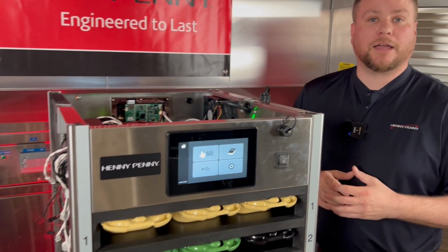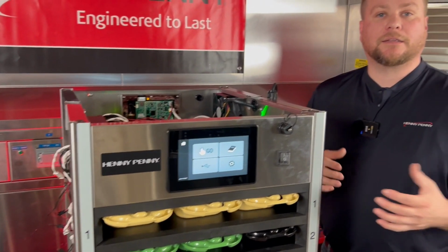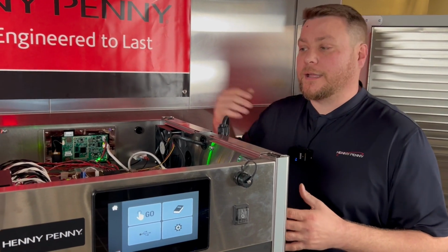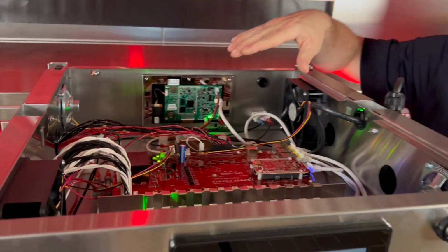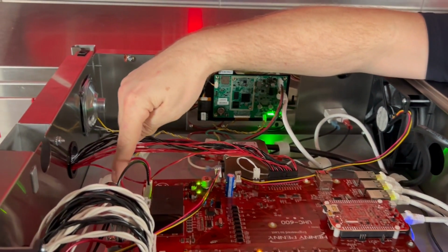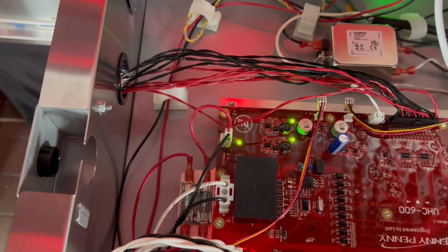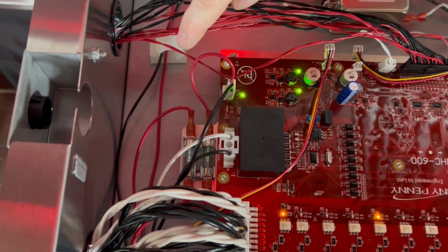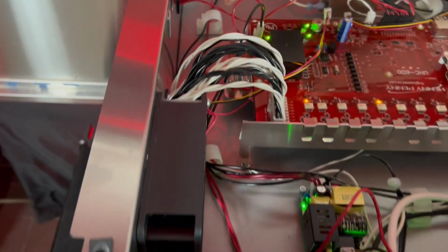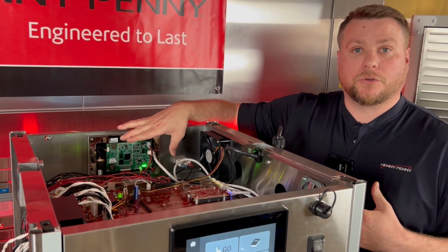However, they will still have access to the control panel so that they can continue to use their timers and navigate throughout the control. Now, when it comes to troubleshooting that, likely we're going to have a situation on the E-220 error code where potentially maybe one of our fuses over here, which is the power supply for our 12 volts DC going to the controls, if one of these fuses is blown, then it will not deliver the 12 volts DC powering up the control board.